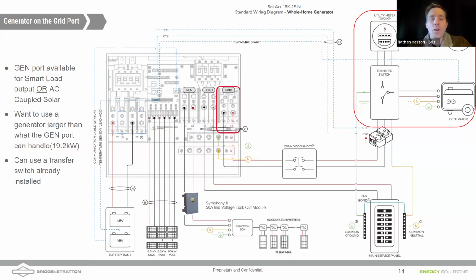So you can do a few things. Sol-Ark recommends that you program your generator to only run at times when solar is not going to be available, nighttime for instance. With Briggs & Stratton, we have these lockout modules. If you're using one of our transfer switches, you can just install a line voltage lockout module like shown there. That's only about $100 to $150 for that part.